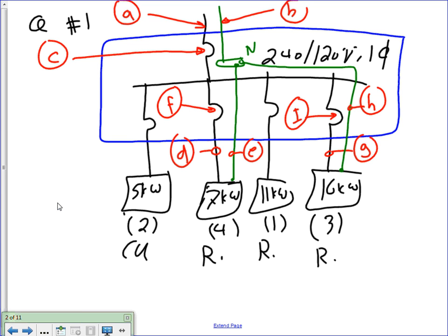Voltage drop recommendation in the NEC code book. Anybody remember them? On feeders and branch circuits. That would be in Article 210 and also 215. 5 and 3 percentage. It's actually in 2 locations, in 215 and also 210 for branch circuit. And it's an information note only. Different for feeder or branch? No, same note. Same 3% and 5%.